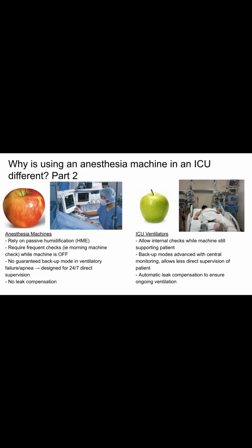So they're not really comparing apples to oranges, but they are definitely different apples. Our anesthesia machines have passive humidification, often done with an HME. We're not sure how well that will fare out for long-term humidification of airways and preventing drying of secretions that could become mucus plugs. Our anesthesia machines are supposed to have a daily machine check while the machine has been powered down. There is no way to back up the patient's ventilation during this period. Also, if there is ventilatory failure or patient apnea, depending on which mode you have set, there's no guaranteed backup rate that kicks in. They're really designed, as you can see in the picture there, for an anesthesia provider at the bedside the entire time for supervision.